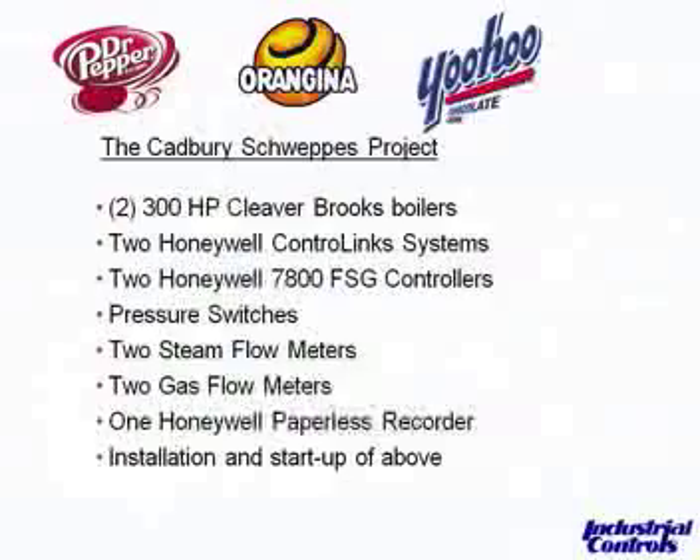At Cadbury — now known as Dr. Pepper — they make Orangina and Yoo-hoo at this plant. They have two 300-horsepower Cleaver-Brooks boilers, gas-fired. We put in two Honeywell ControlLink systems and found during the site walk that their flame safeguard equipment was obsolete, so it made sense to install the new Honeywell 7800 flame safeguard controllers and upgrade the pressure switches. The customer also wanted to measure steam output to their process, and due to NJDEP requirements, individual gas meters were required for boilers over 5 million BTUs per hour. The steam and gas meters fed a Honeywell paperless recorder that sends fuel usage data over the customer's network monthly.